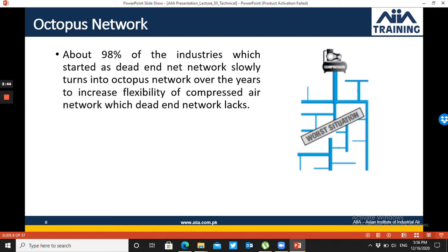Different piping materials are used, different diameters are used, and everything is connected to the same system. This results in sharp bends, different diameters, and different materials in the piping network. As a result, pressure drops increase and flow losses increase, requiring a bigger compressor which increases electrical energy losses.